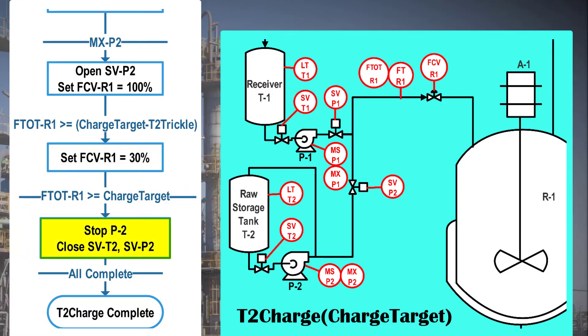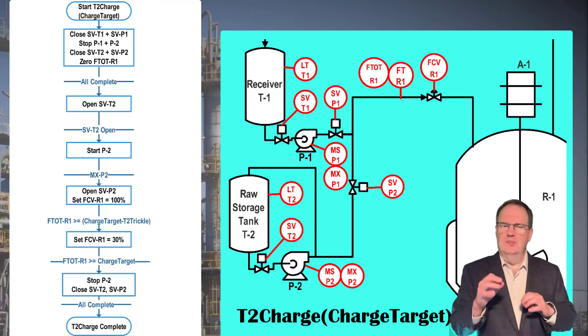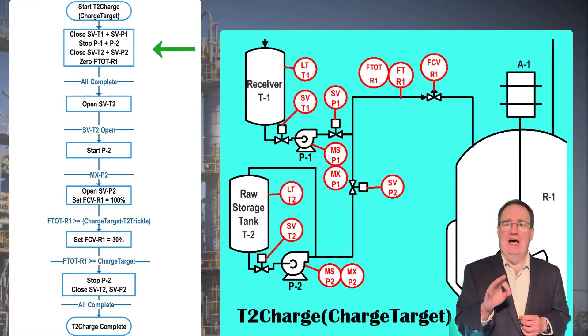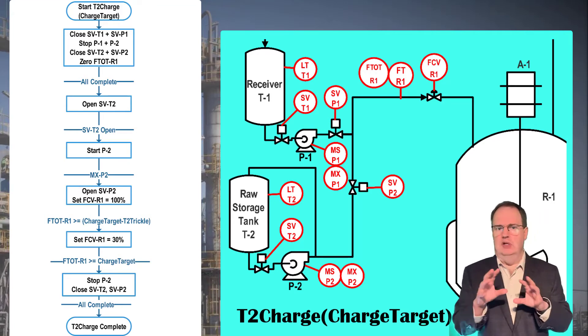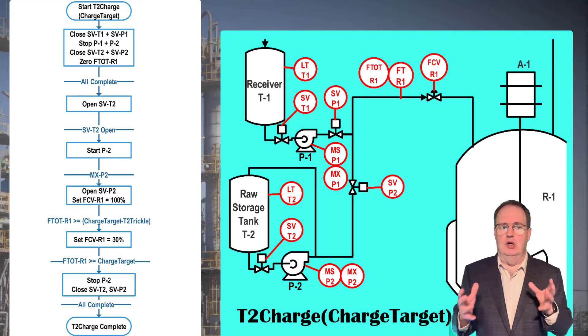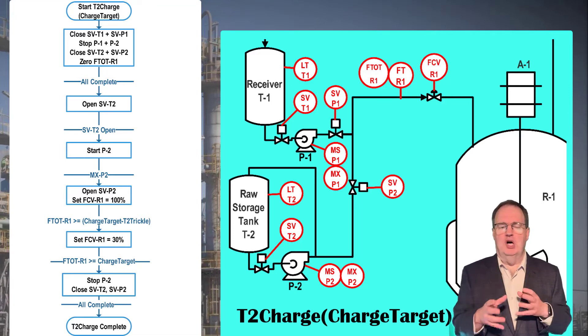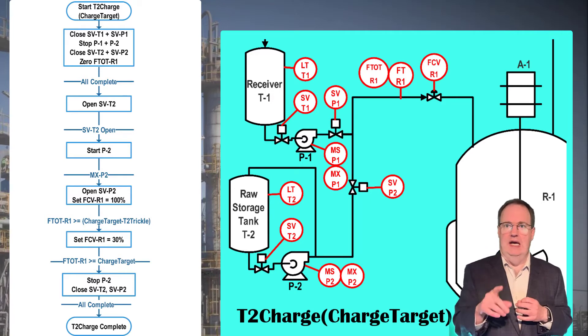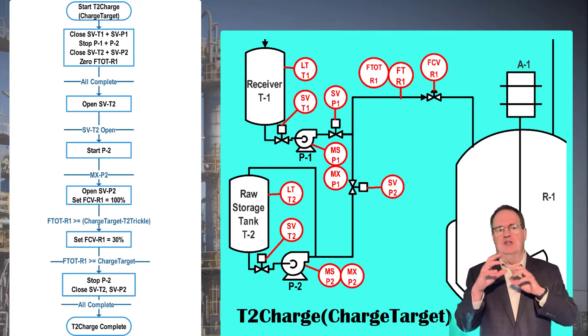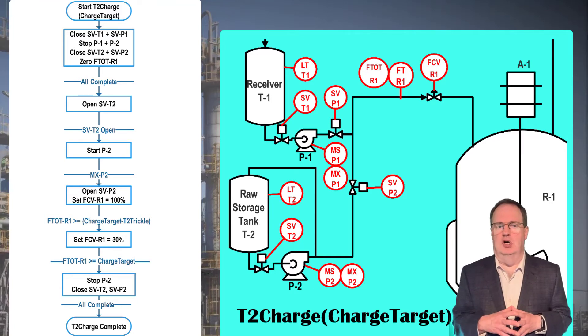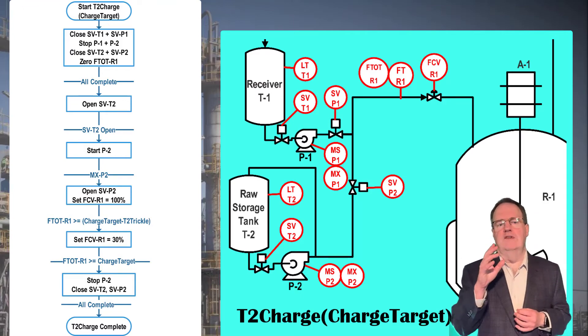With the charge complete, we shut everything down. That phase is correct, but it could be better. We shut down everything in the equipment module as our first action, but then just assume that everything the phase didn't move stayed where it was supposed to be — that is bad practice. Valves and pumps can be adjusted manually by operators, and we shouldn't assume they haven't been, particularly if something failed and the phase got stalled at a transition. A handy design tool is therefore a phase state table.